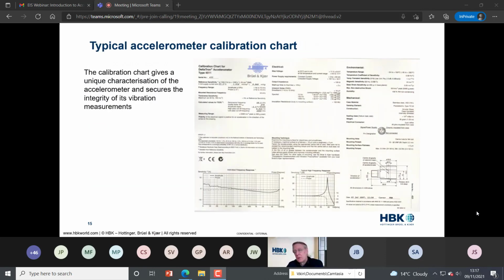What I've got here is a typical accelerometer calibration sheet. This happens to be for an IEPE type. And if we look on here, we've got a section on the sensitivity and the mounted resonance. We've got a section on the electrical performance. An important section here on the environmental influences and to what degree different environmental conditions will affect the accelerometer's behavior. We've got mechanical and then frequency response in both phase and magnitude.